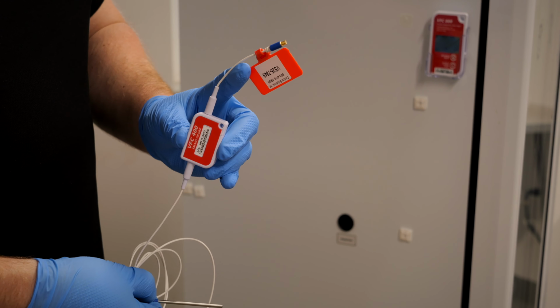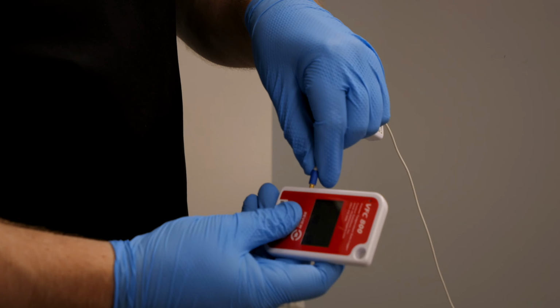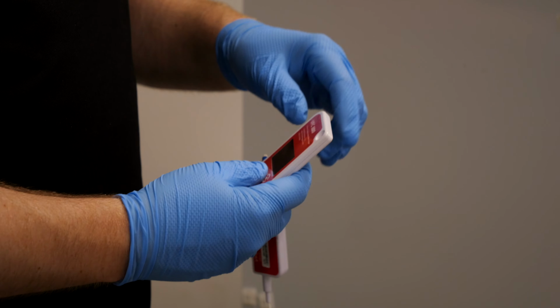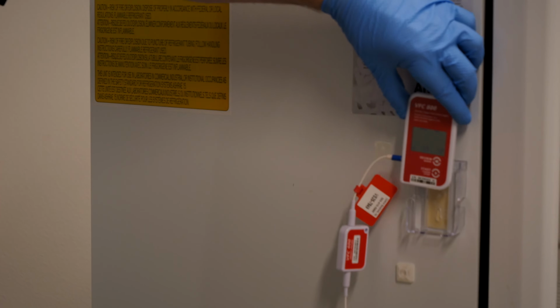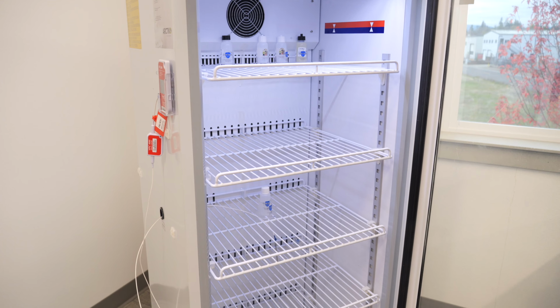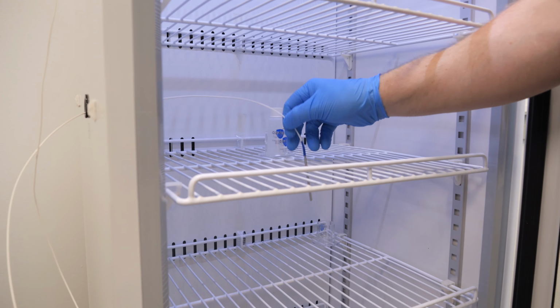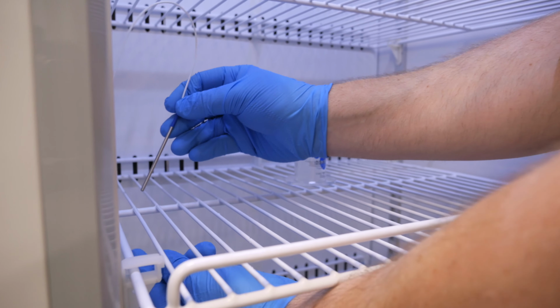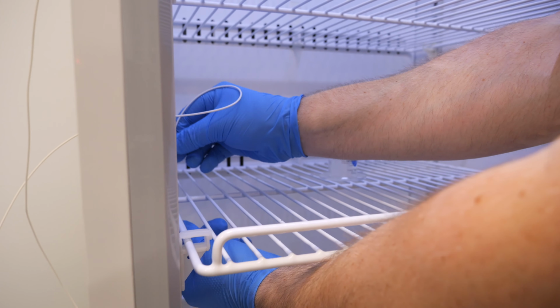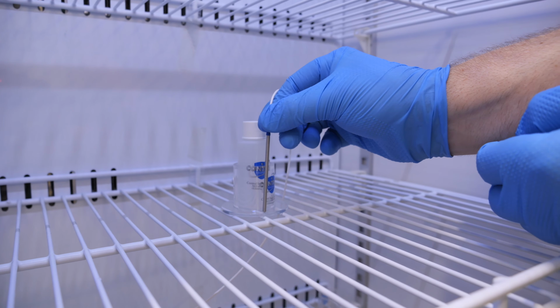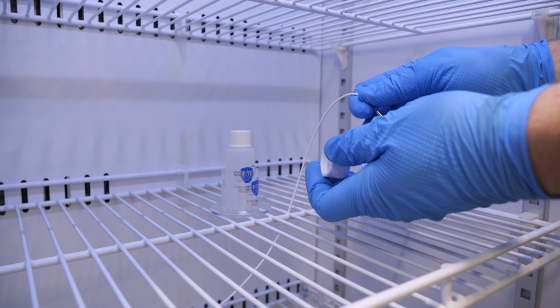I'm simply going to connect the probe to our logger. And I'm going to rest the logger into the wall mount bracket, which is set up in a way that allows you to remove and insert the logger within the bracket even if the probe is connected. So now that we have our probe inside the refrigerator, we will install the probe. With these cables, they're best fished under the racking, and we like to pull them through above and then get them to where we like them, to where they will meet your bottle.